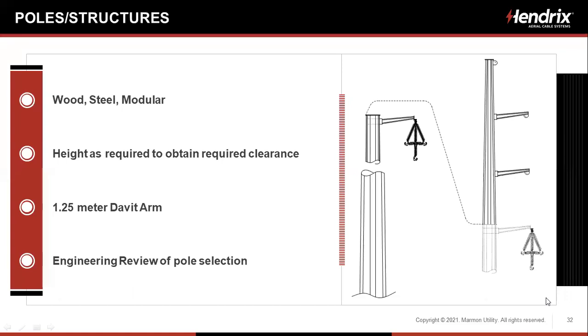As far as poles and structures, at 26, 27 years in, we've installed 69 kV on basically every type of structure there is out there on the planet: wood, steel, modular poles. We're using the height as required to obtain the required clearance. You can see the davit arm there. Our standard davit is 1.25 meters. And we also will do engineering review. Either we'll select the pole for you, or we'll do an engineering pole verification for the poles that you select.